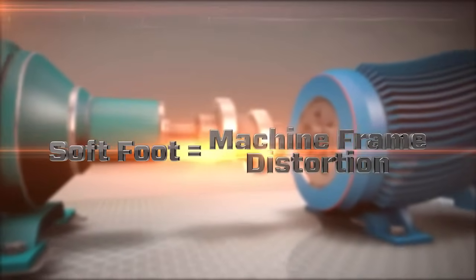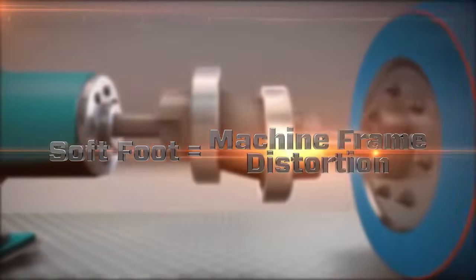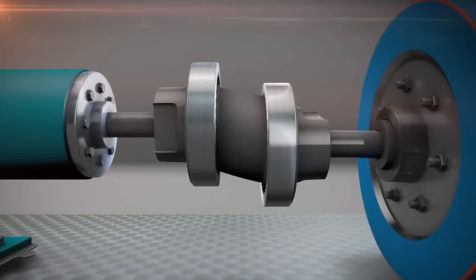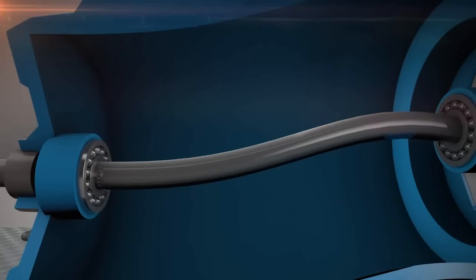Soft foot means machine frame distortion that occurs as the machine's hold down bolts are loosened or tightened. Distortion of the machine frame leads to misalignment at the coupling, internal misalignment of the bearings, increased radial load on the bearings, and a deflected shaft.